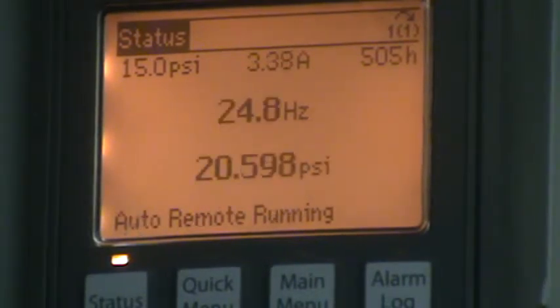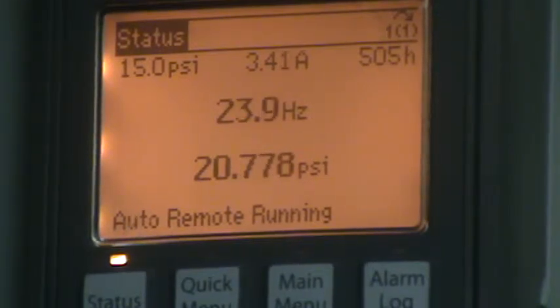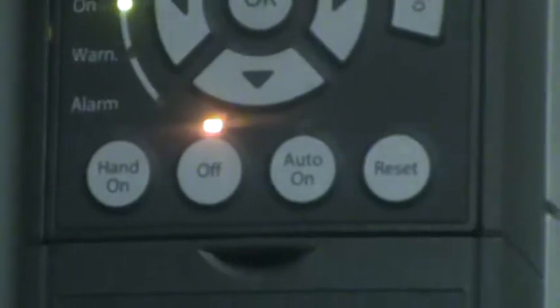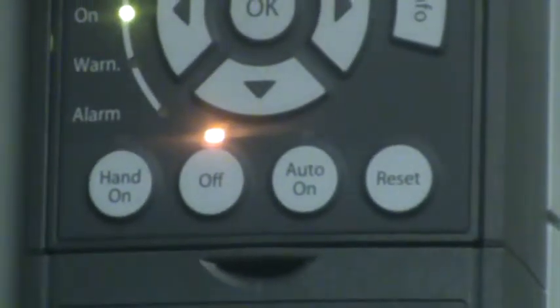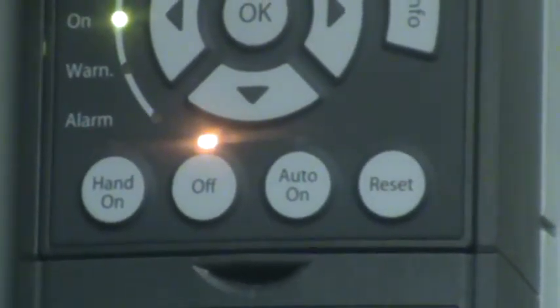You can go directly from hand to auto. Once you put it in auto, it'll look at the transducer and say, what should I be doing? And just start doing it. If you're above the speed, it'll just slowly come down to it. If you're below it, it'll slowly come up to it.